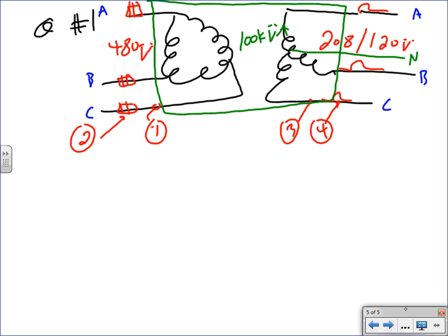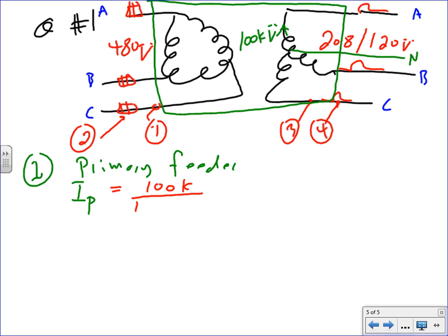All right. Any question, guys, about this typical transformer? I'm going to start by number one, the primary feeder. To find the primary feeder, I need to find I primary. You remember how we find I primary? You take the kVA of the system divided by 1.73 times what voltage on the primary side? 480. So you need to find the current, and that will get you a healthy 120 amp.